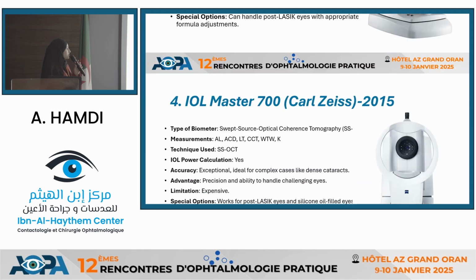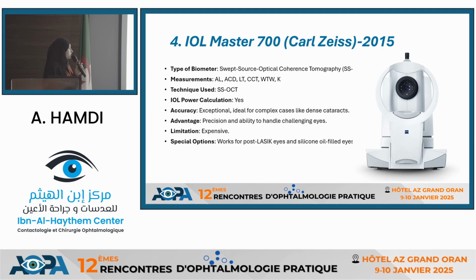Next, we have the IOL Master 700, one of the most known devices on the market. It was actually the first one that uses the swept-source OCT technology. This technology is known to penetrate well denser cataracts, and it also gives us a very good imaging system. We can see the whole ocular structure, including the anterior chamber, the fovea, and the cornea. So it's very reliable for IOL calculations, but it's a bit expensive compared to other devices.